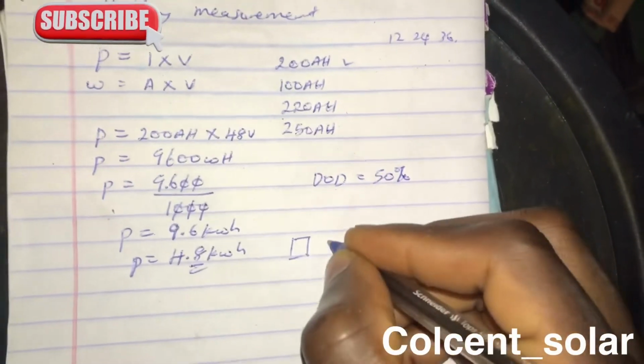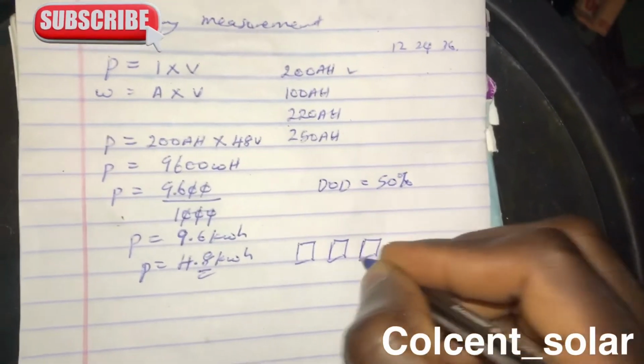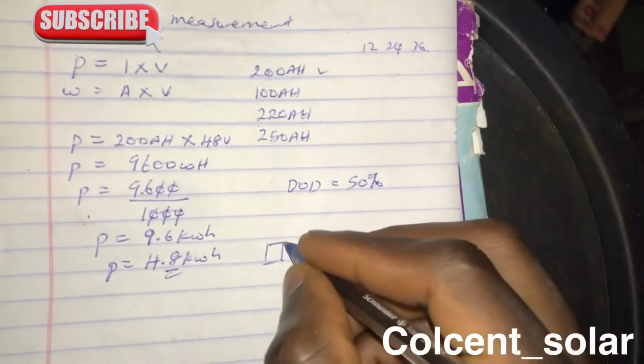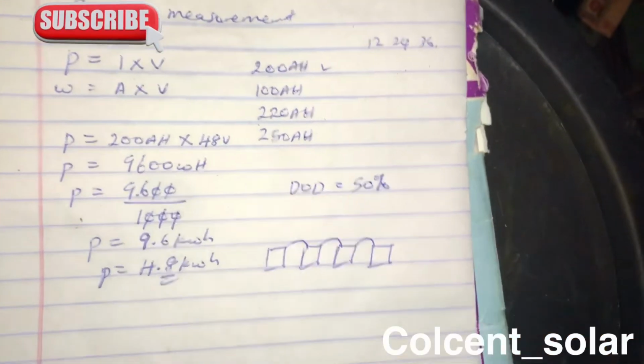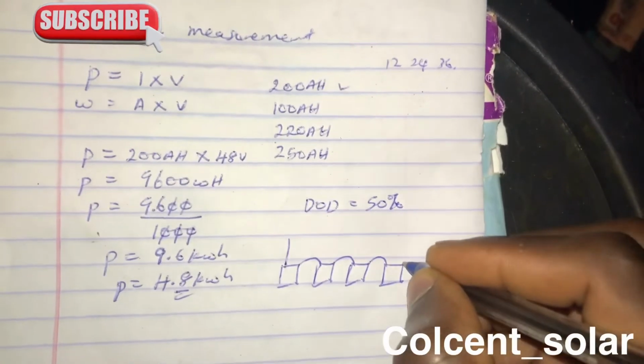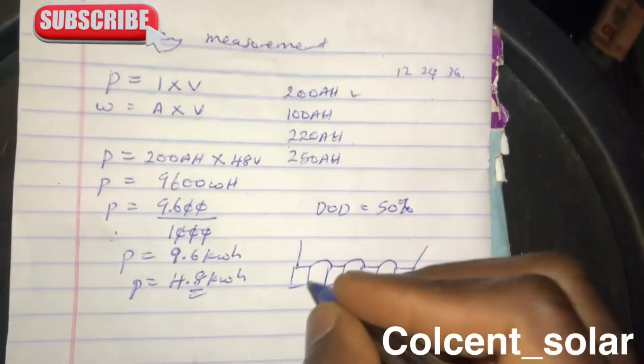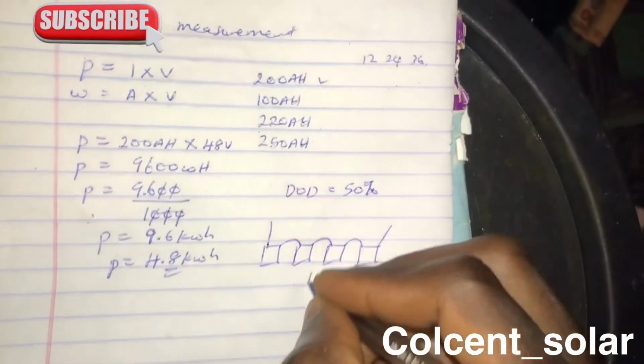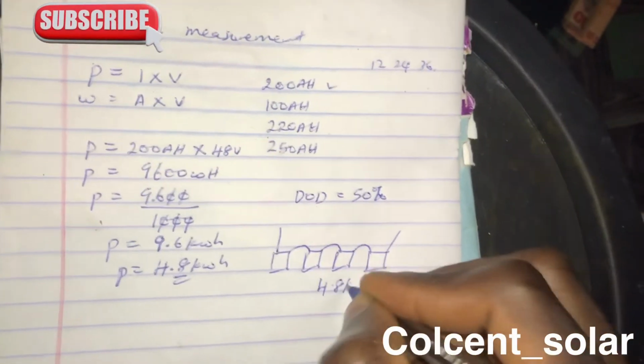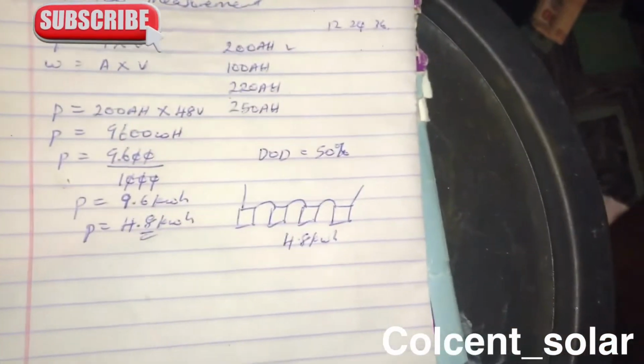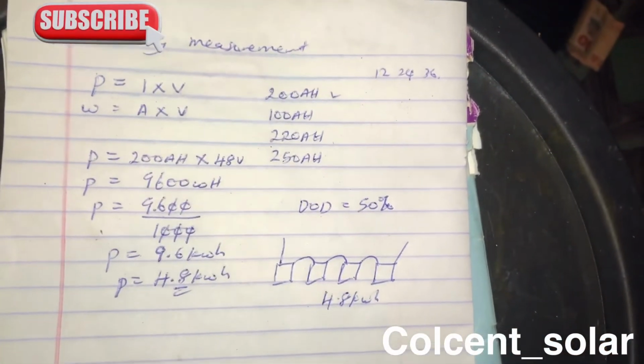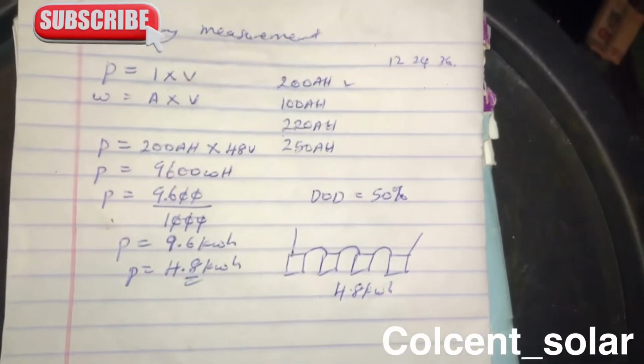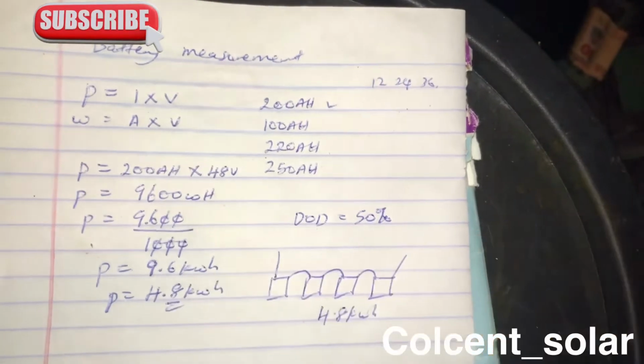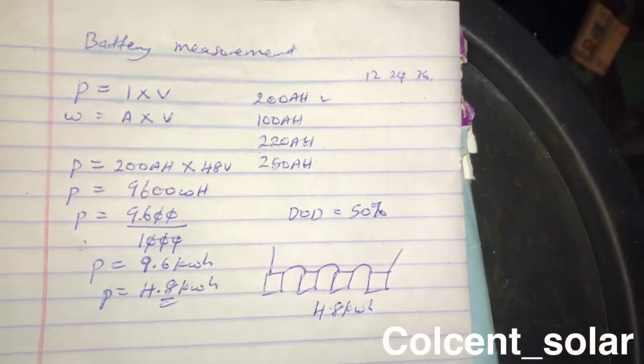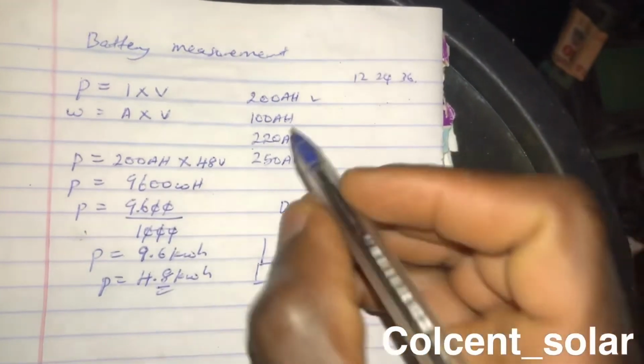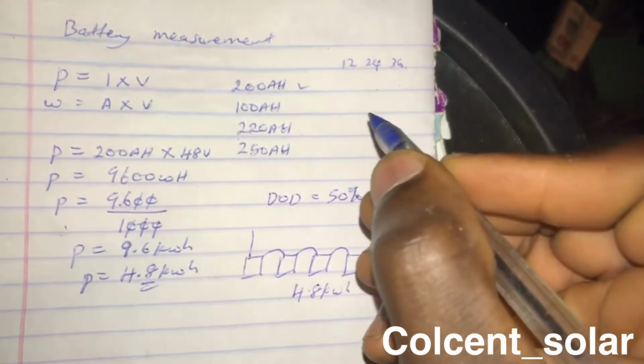So 4 batteries, whether lead acid or wet cell, 4 batteries of 200 amps, 12 volts connected in series to give you 48 volts. The actual power it contains is 4.8 kilowatts. So in case you see lithium batteries of 5 kilowatts, you actually know that it's just equivalent to 4 batteries of 12 volts, 200 amps. But calculating with 220 amps, it will be slightly bigger.